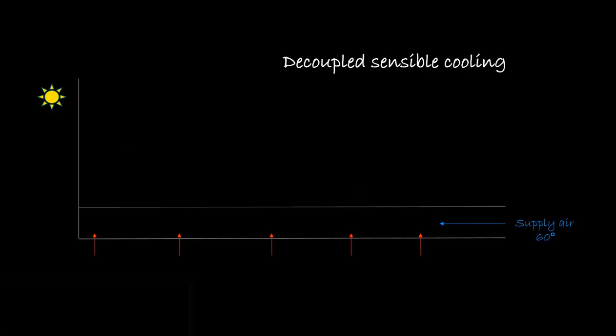Another way to minimize the effects of thermal decay is to reduce the sensible cooling responsibilities of the plenum air. This can be accomplished by ducting the supply air directly to the perimeter zones or by using decoupled sensible cooling devices, such as passive chill beams.